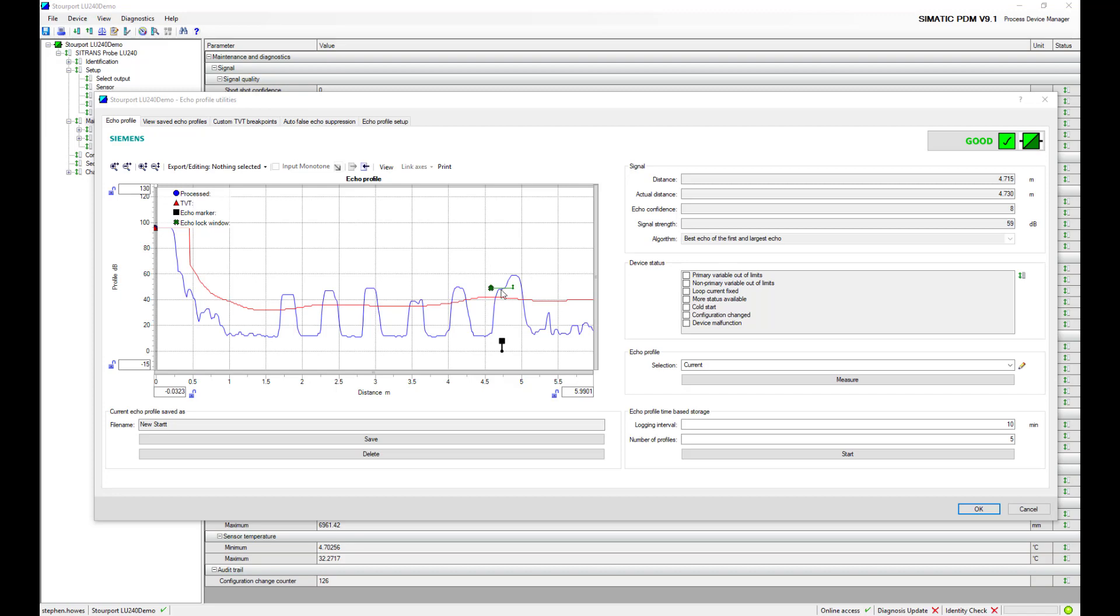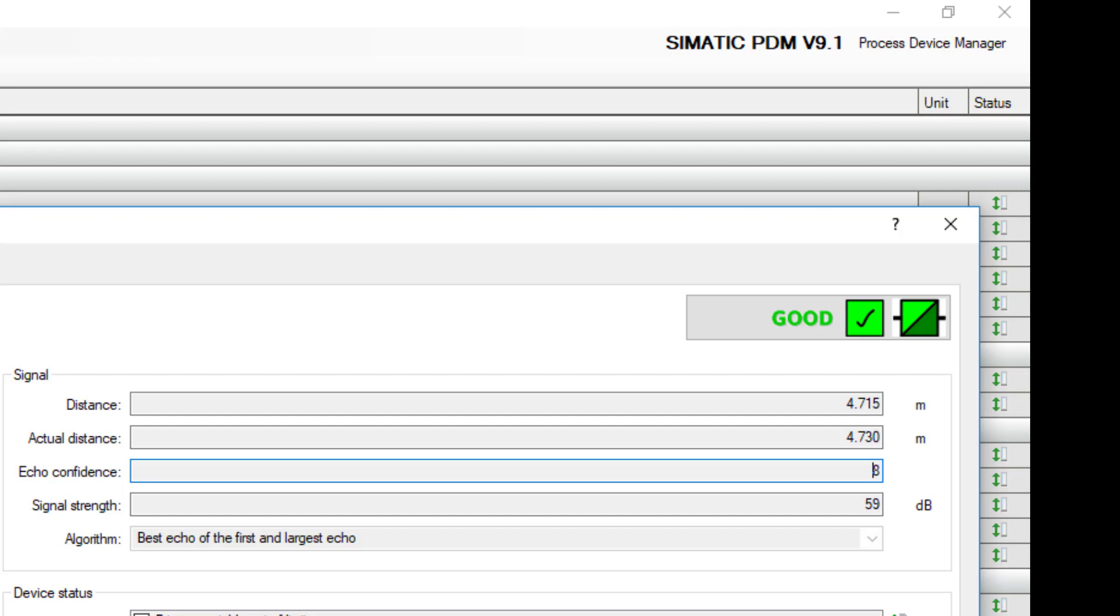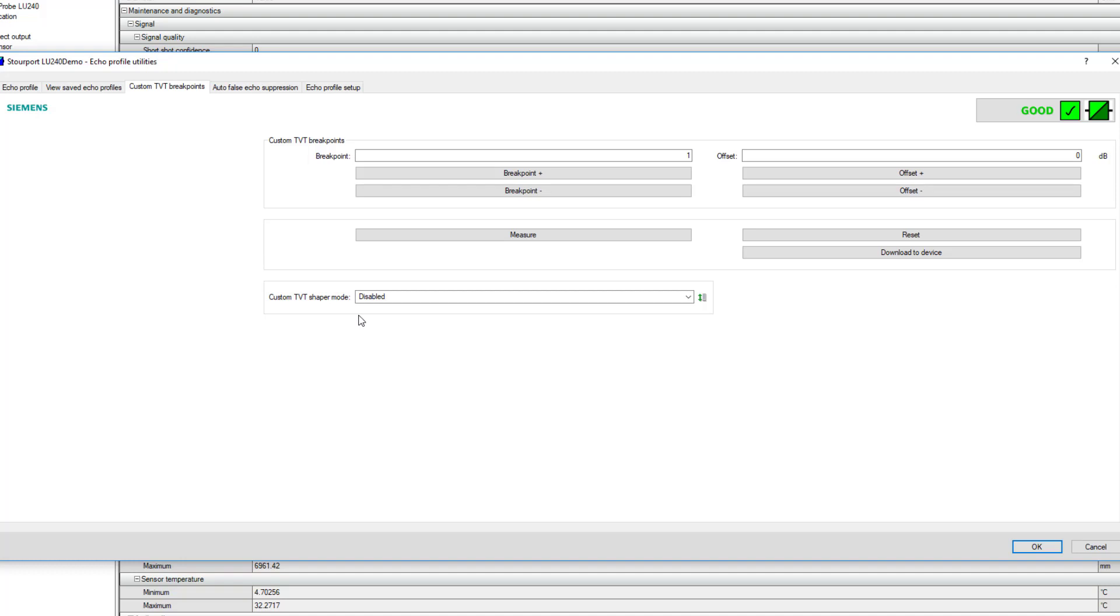We have the signal strength and we also have the confidence. This particular signal isn't brilliant, it's not bad but it could be improved. One of the ways to improve it is to shape around these blue what we call false echoes, and you can do that automatically or what I'm going to show you now is manual TVT shaping. This is an exercise you don't have to do manually but we're going to do a little bit of manual TVT shaping.